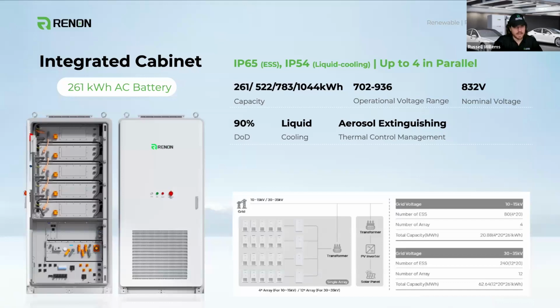It has a lot of flexibility. It's one of my favorite systems because it's a great AC coupled add-on for existing solar systems or diversity of use cases. You can run solar directly into it. If you're doing a new install, you can run the DC fast charger directly out of it. You can run solar, you can do instantaneous changeover, so it's good for data center backup as well because it has a sub 20 millisecond changeover time. So really great product, a ton of flexibility in terms of use case. A lot of different ROI validation approaches and gives you a lot of flexibility depending on whatever your use case might be. It's a pretty concise or compact form factor, so it gives you a lot of choices when it comes to charging or placing them in different places.